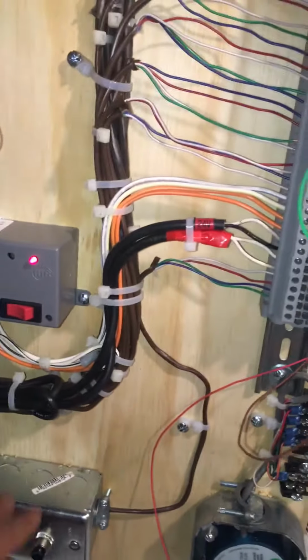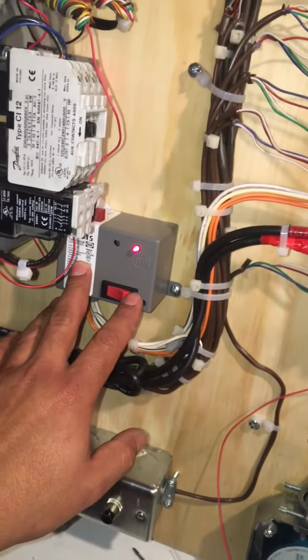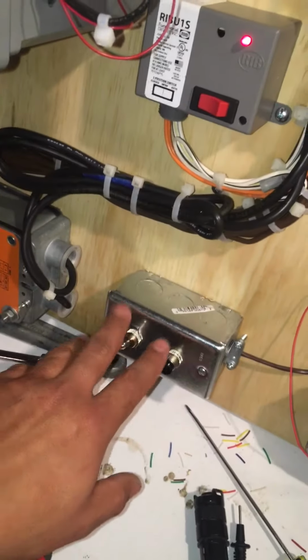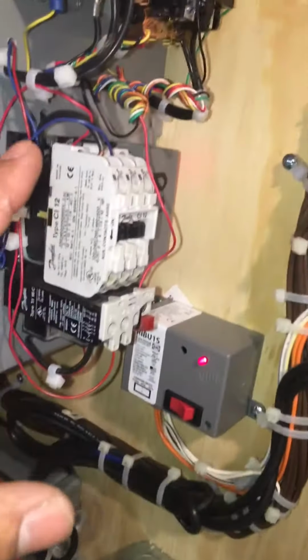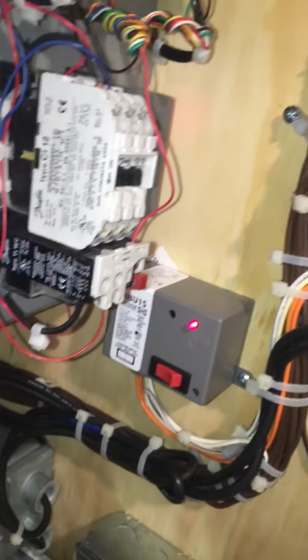But usually we won't see the HOA switch in the circuit at the same time that the start stop switch would be wired in using the auxiliary contacts of that contactor. But that's all in a nutshell.